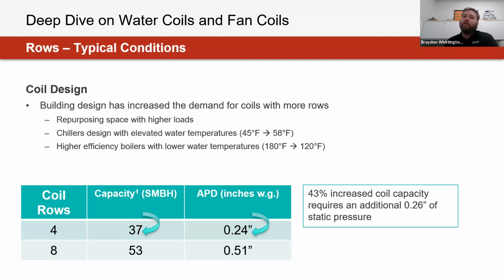I mean, there is the reality as we start to get really into the nitty-gritty, and I feel like that could be its own class in terms of the influence of dampers on a VAV within a given system or other potential choke points. But with a lot of this performance, especially when we tie it back to fan coils and blower coils, these are actually under their own program of being tested as a full assembly. So adding additional length to it is potentially not really going to make a difference, because it's already been tested as full equipment with both the fan and the coil in conjunction with each other. A really good question there.